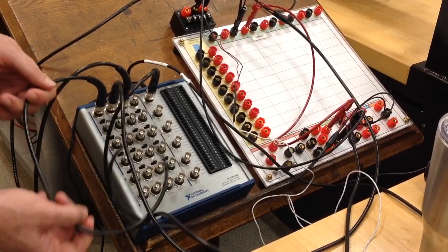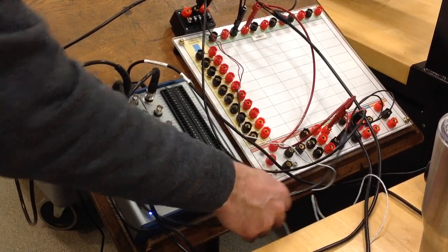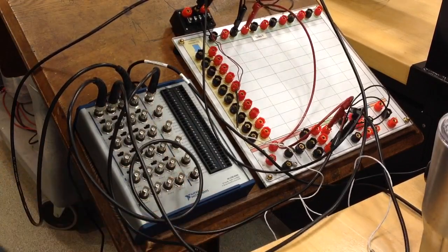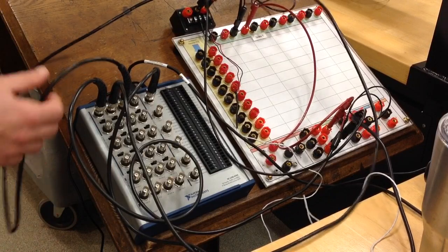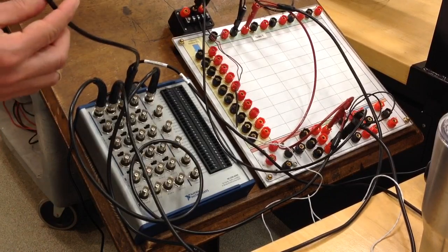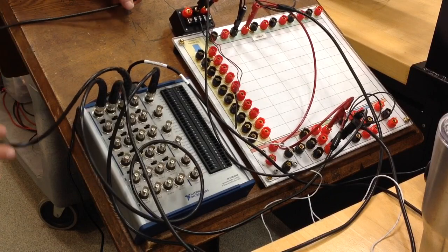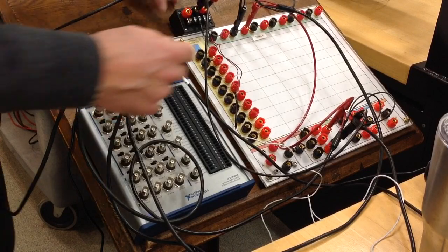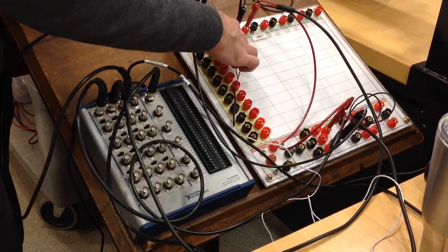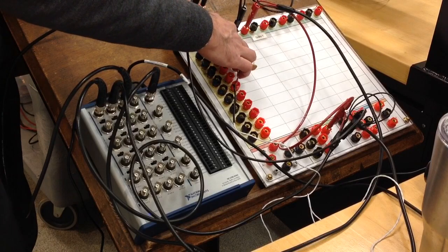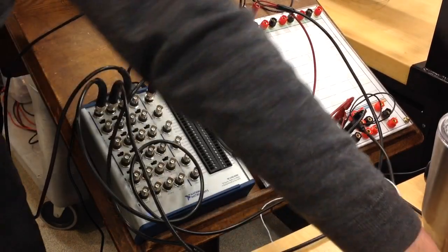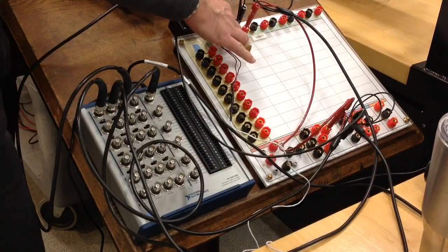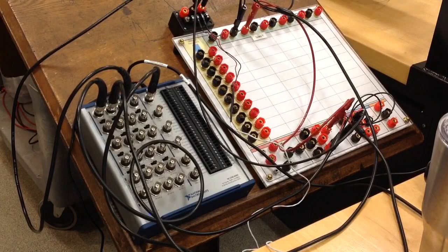So now I have three analog inputs here. The first one is measuring the excitation voltage. The second one is measuring the voltage drop across the reference resistor, and the third one is measuring the voltage drop across our RTD. Okay, so you have every voltage information for your setup. So one key point here is that for this reference resistor, the resistance value should be close to what you are measuring. So remember, this RTD is measuring around 100 ohms, so this has to be around 100 ohms as well. Okay, so it's one key point.